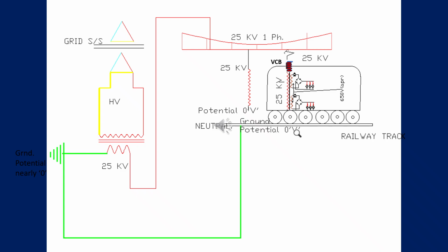So we are using the smoothing reactor to make the DC current smoother, and then we apply it to the traction motor, a DC series motor. The motor rotates and is coupled with the wheel with some arrangement, I will tell it later, and the wheel will rotate. And another supply we have taken, I have already told, is another winding for auxiliaries. We are taking 380 volt, here 650 volt and there 380 volt. Then we are converting the single phase into three phase to run three phase induction motors as auxiliary motors.